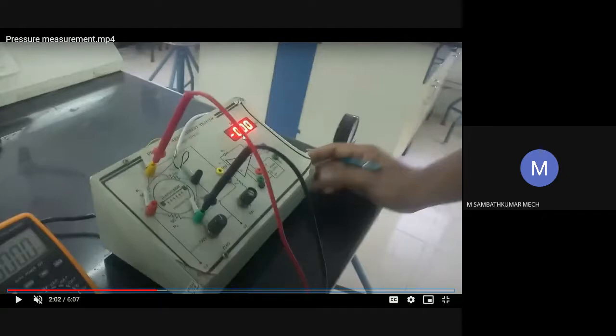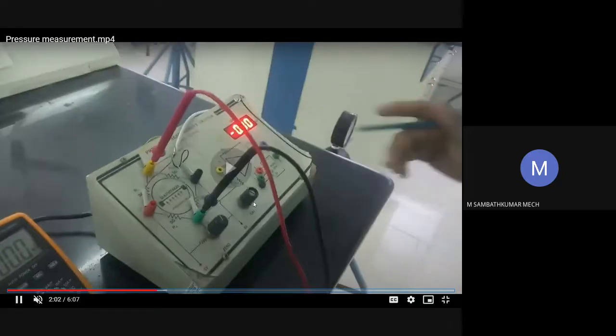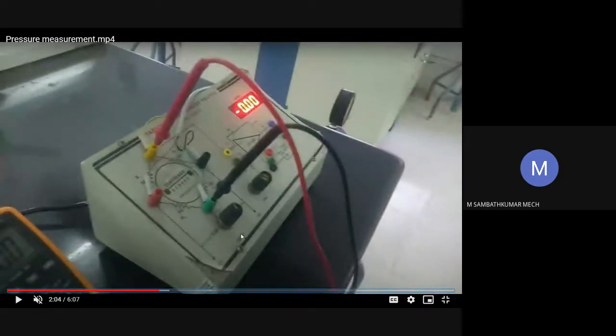For correcting this, at the bottom of the trainer kit there are two knobs. One is a 0 knob and another one is a calibration knob. When you adjust the 0 knob, the range varies very largely. If you want to correct a minute change, you can use the calibration knob to set 0. When you rotate the calibration knob, the value changes only minutely. If you change the 0 knob, the value changes hugely.